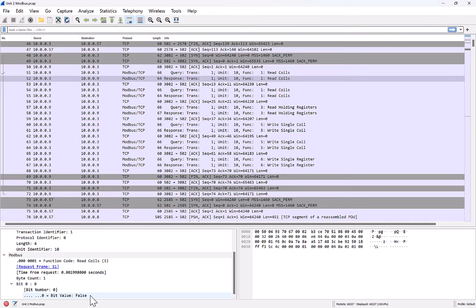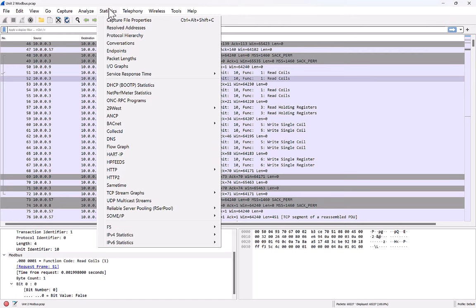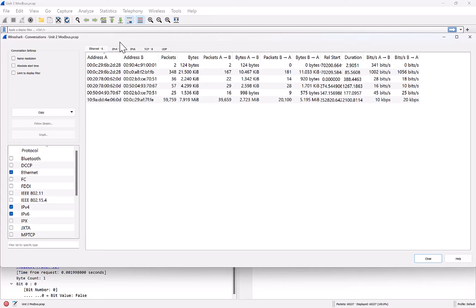Real quickly, just to add, because a lot of conversations in ICS-OT environments talk about using packet captures to create asset inventories. So how can I see what's out there? There's this statistics menu. There's a couple options, but we're just going to look at one for right now. I can go and look at conversations. You can see that Wireshark parses through all that data. And then it tells us, we saw basically these six different conversations on the network saying, here's the source MAC address and here's the destination MAC address. So who's talking to who? And here's the MAC addresses.